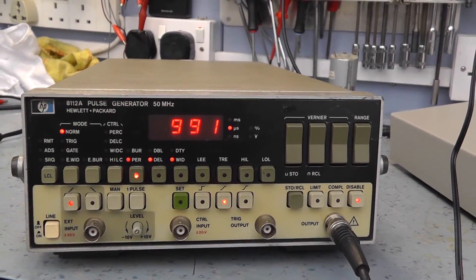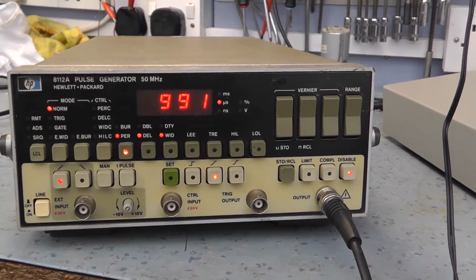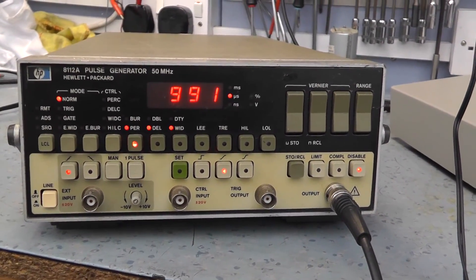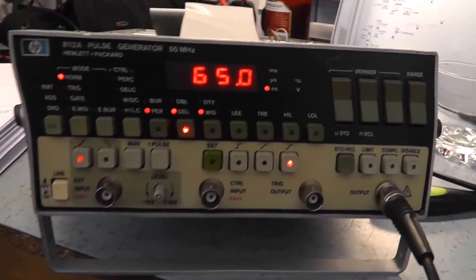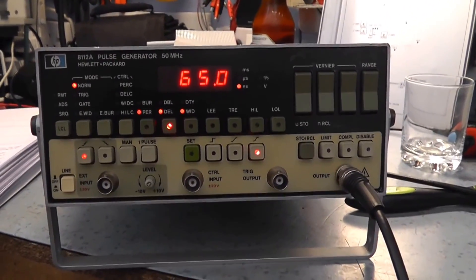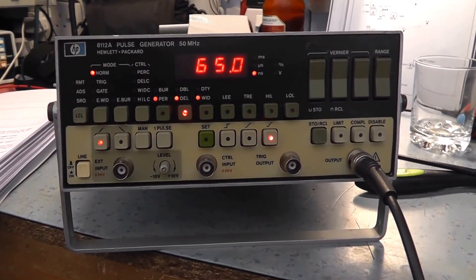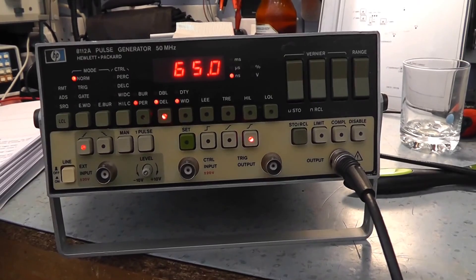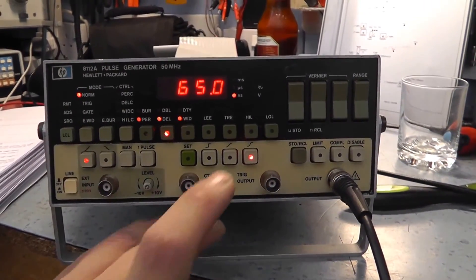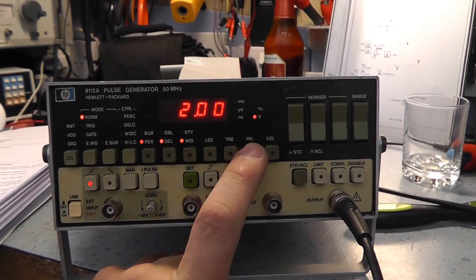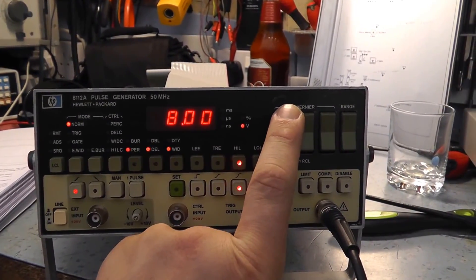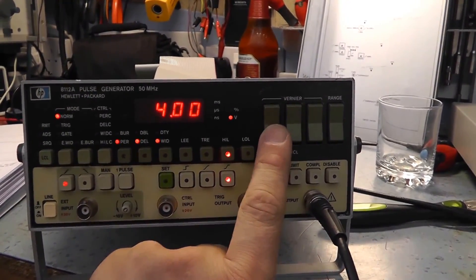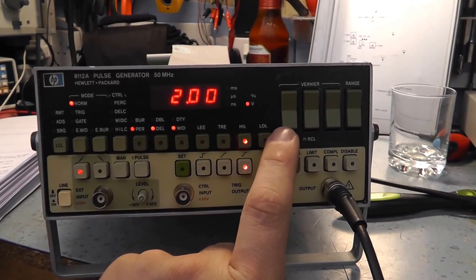So we'll have to do some proper checks on it to see if it works. But this is the HP pulse generator showing some signs of life. And it seems to be working more or less okay. The E41 is a problem with the output amplifier, it suggests. Now the output's obviously clearly okay, and it does suggest that if that E41 comes up, I can't get an output level up to 9 volts. And I can confirm that. This is high level output, HIL. If I increase that, it will only go to 8 volts. It won't go any higher. That's not the end of the world, to be honest with me.